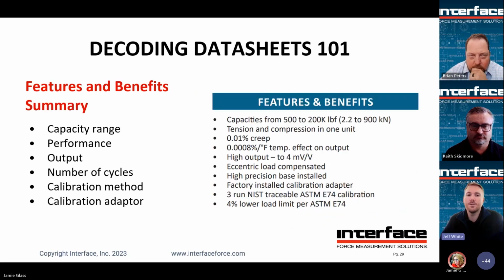So first, features and benefits. Capacity range. Be sure that we're looking at a model in which the force value you need to measure falls within. We will talk about how to size your load cell appropriately. There will always be a trade-off between capacity and resolution. We need to be sure that we size the load cell appropriately to make sure we don't overload the cell, but be sure that we can also measure the smallest increase that you need to see.